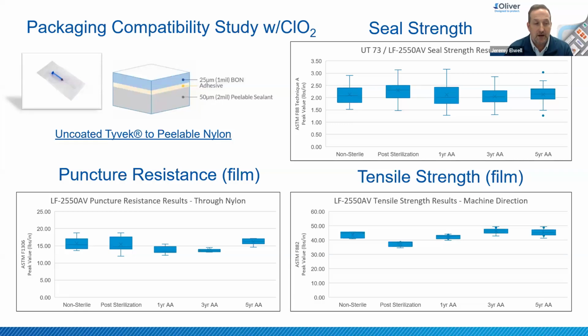First, this is an uncoated Tyvek to peelable nylon pouch. The diagram in the upper left-hand corner is a detailed breakdown of the layers of the film. The outside is biaxially oriented nylon. This is an adhesive lamination, shown by the adhesive in the structure. And on the inside, in the interaction with the Tyvek, is a peelable sealant. These results show seal strength, puncture resistance of the film, and tensile strength of the film, starting with non-sterile, post-chlorine dioxide sterilization, and then over accelerated aging time points of 1, 3, and 5 years. This box and whisker plot of all of these shows not much effect over time or by the chlorine dioxide sterilization. So with this combination, we're very comfortable recommending it for this application.